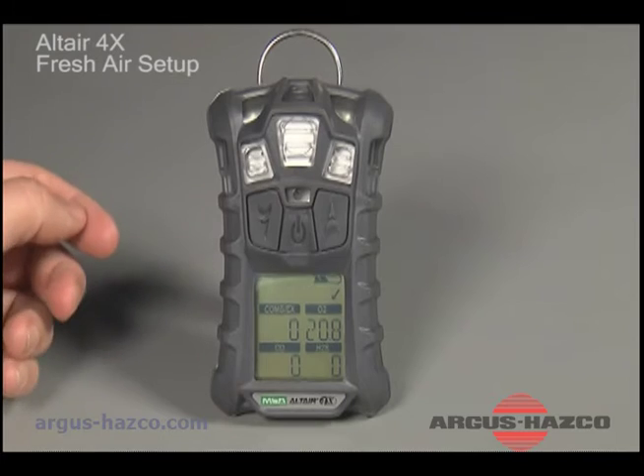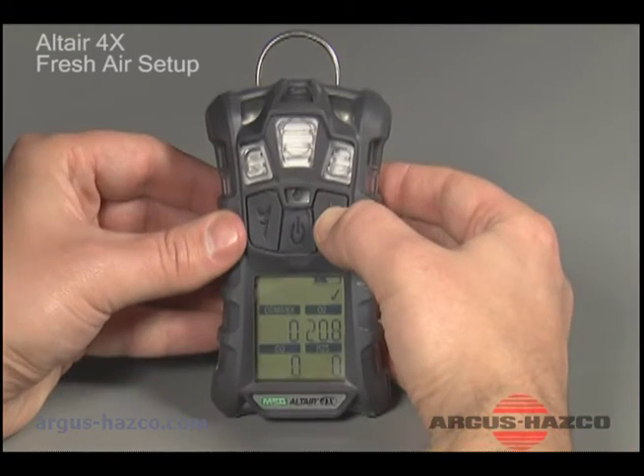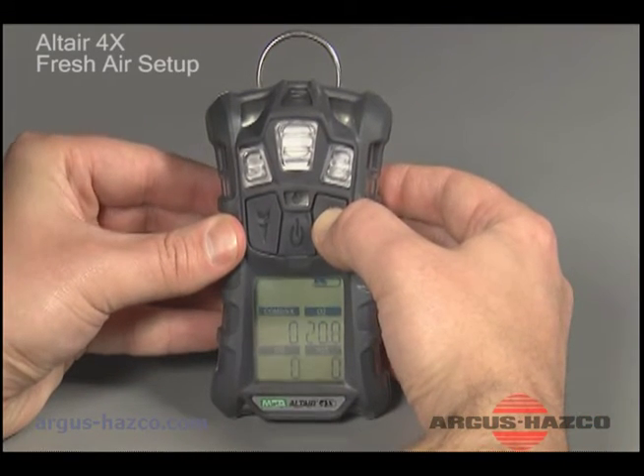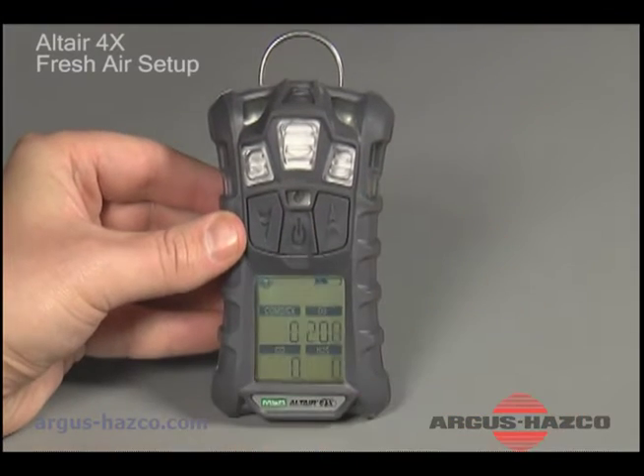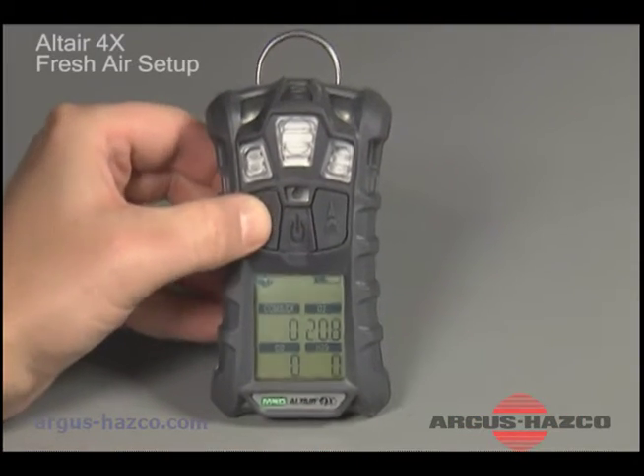To perform Fresh Air Setup from measure mode, simply hold the Page Up button for 3 seconds until 0 cal displays on screen. Next, press the Page Down button to perform Fresh Air Setup.